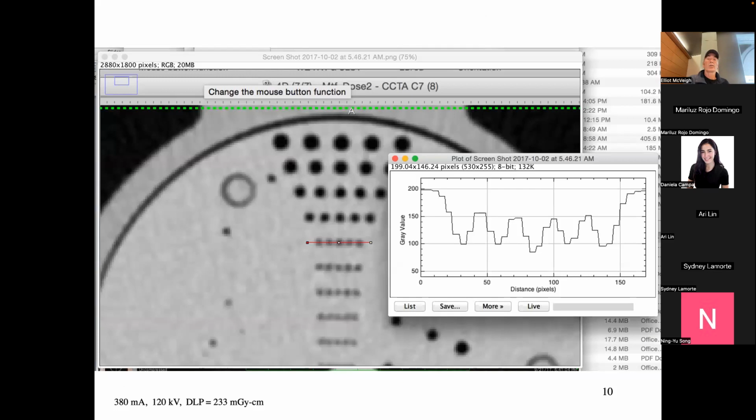So we can quantitatively measure the modulation transfer function on our imaging device by taking a picture of something like this, in this case, CT. We could do it with MR too. And then take a line, and you'll do this for homework using a piece of software. The one that we suggest is called ImageJ. It's a public domain analysis package, which will be posted up.